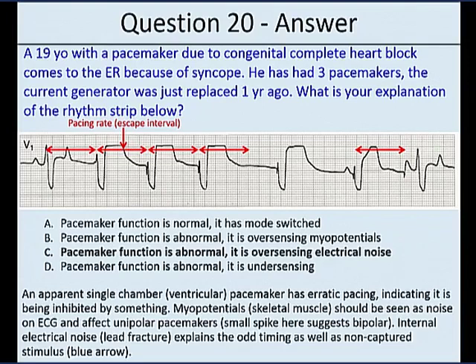Now he's had this lead for a while. I don't tell you that he's always had the same lead, but most of these people do, and you just trick it along as long as you can until something like this happens. Pacemaker generator replacement is a very vulnerable time for leads because they are in the pocket there, they're all scarred up, and sometimes you get in there and you can feel the thing, but man, where is this? I'm dissecting around, it's just a big bucket of scar, and finally break into the scar and do some cautery. Insulation on leads doesn't like cautery so very well. So after a couple of times of this, maybe his insulation is broken a little bit, and he's getting some body fluids in and causing some arcing on his pacing leads.